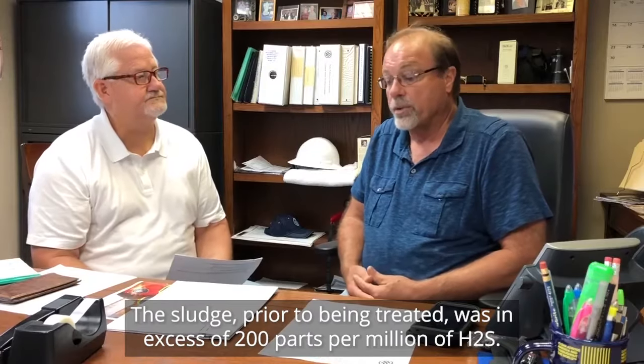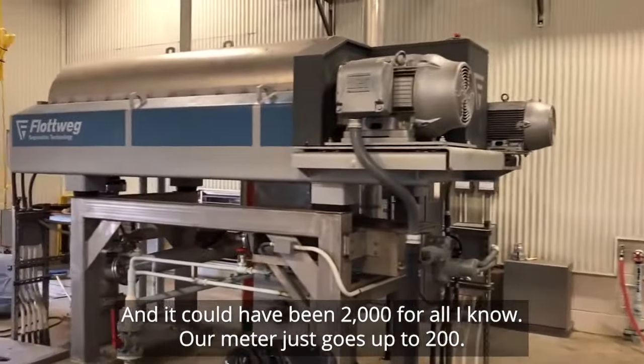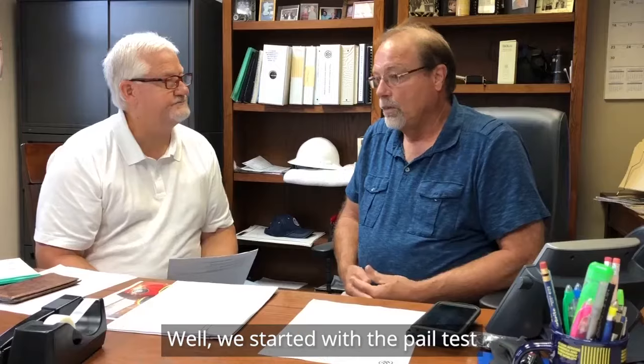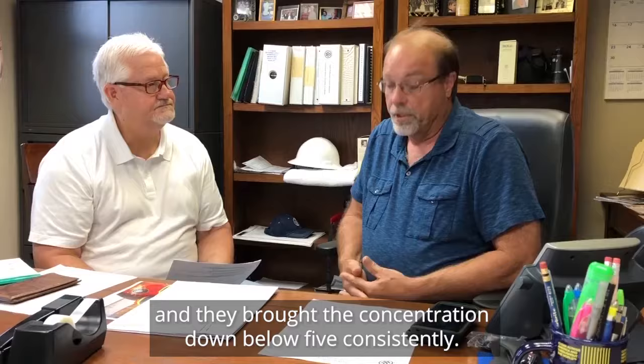The sludge prior to being treated was in excess of 200 parts per million of H2S — and it could have been 2,000 for all I know; our meter just goes up to 200. We started with the pail test, and they brought the concentration down below five consistently, and then also the biological part of things.